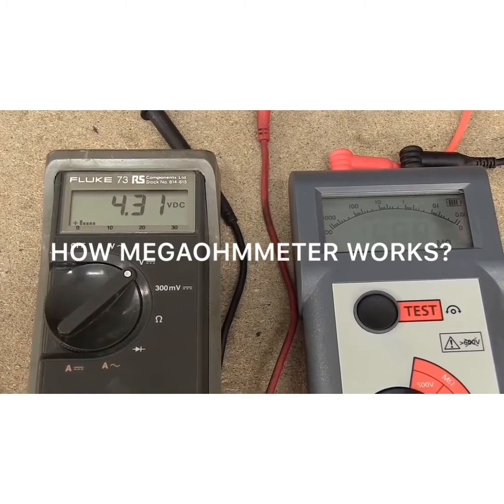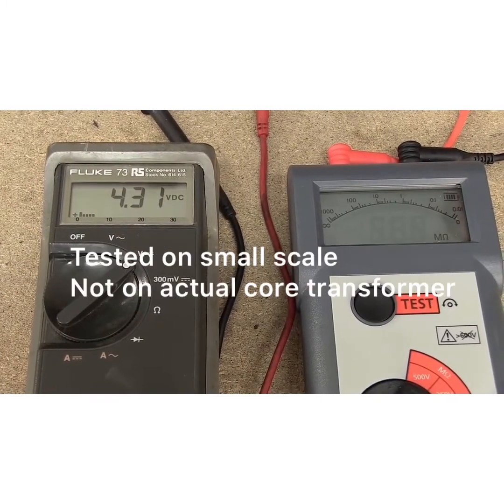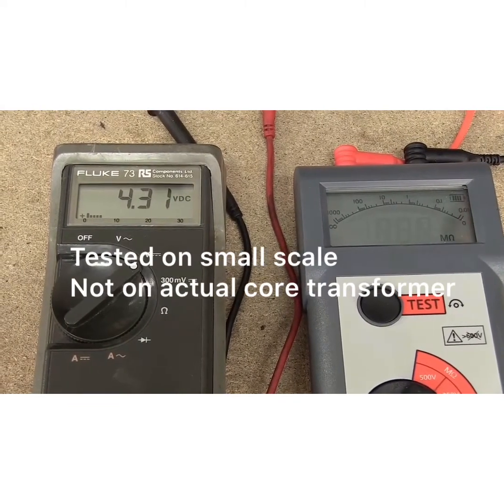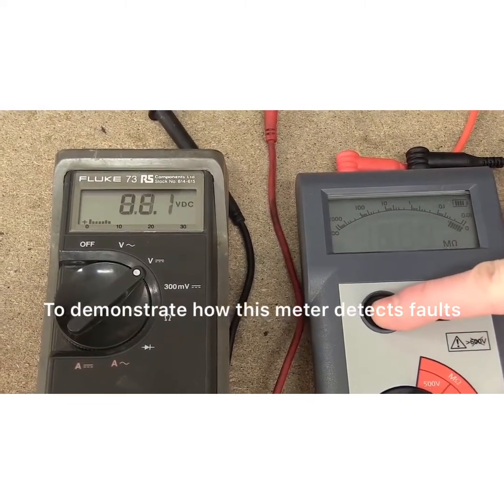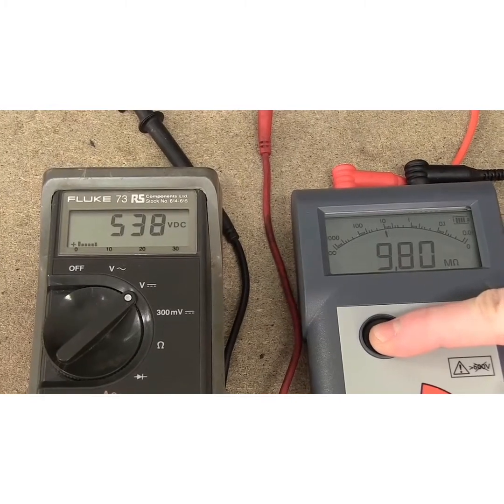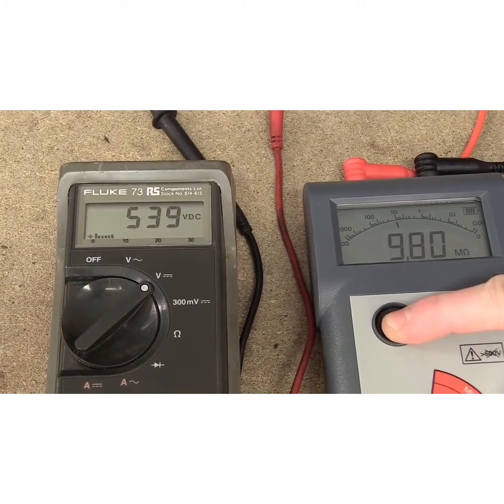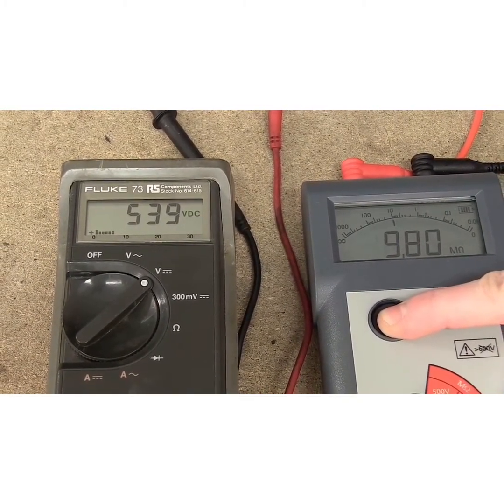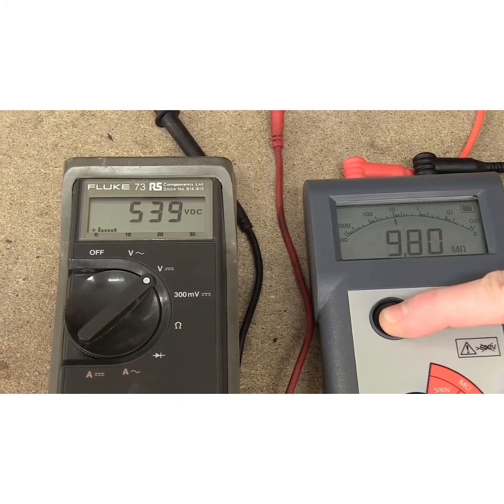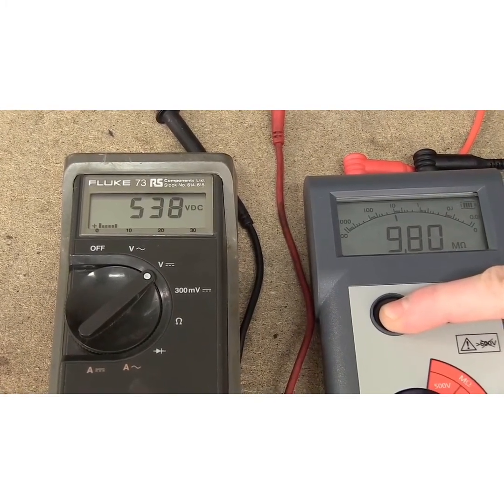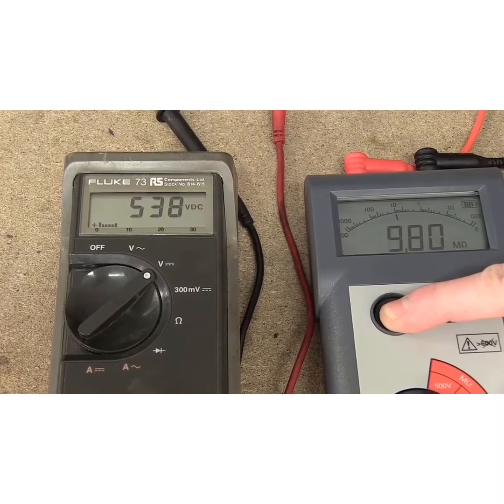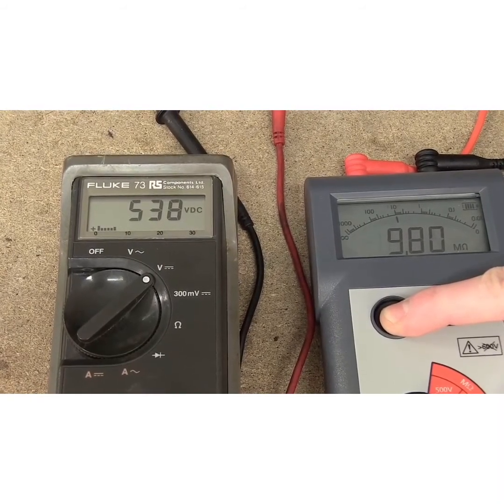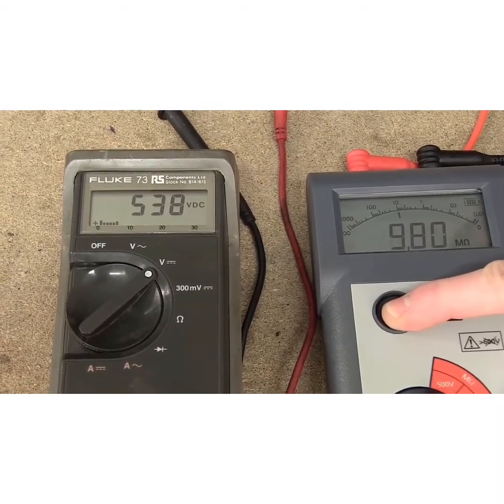A normal multimeter uses a low voltage, but insulation testers use a much higher voltage to test for a resistance leak. If I press the test button here, you can see the meter attached to the Megger is giving a reading of well over 500 volts, whereas a multimeter would typically use 9 volts to measure. Therefore, a Megger is more likely to show a failing element that is tripping the fuse board.